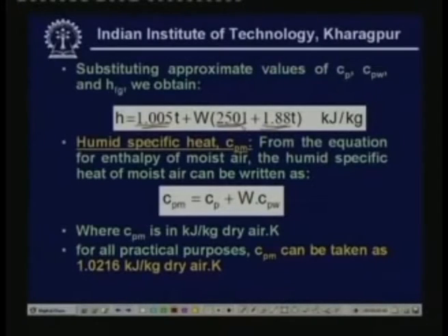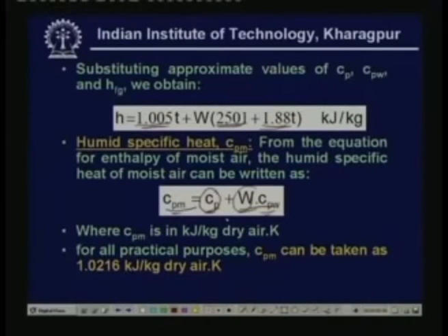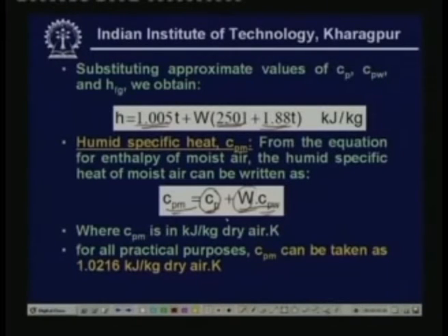The humid specific heat CPM is the specific heat of moist air. From the enthalpy equation, CPM = CP + W·CPw, where CP is the specific heat of dry air, W is the humidity ratio, and CPw is the specific heat of water vapor at constant pressure. The units are kJ/kg dry air per Kelvin. For practical purposes, using a mean value of humidity ratio, CPM ≈ 1.0216 kJ/kg dry air·K.